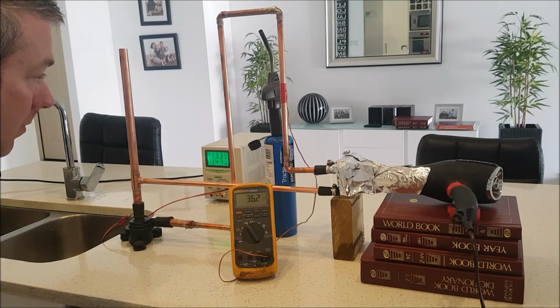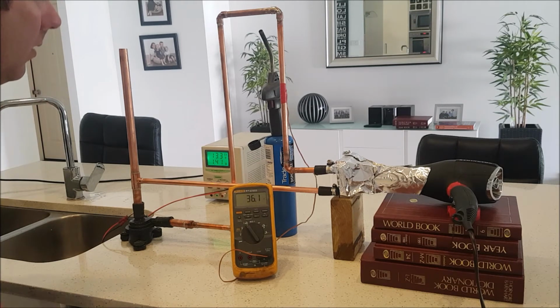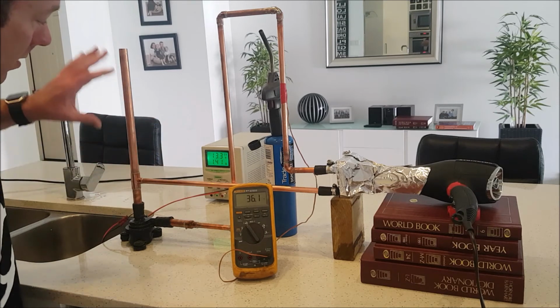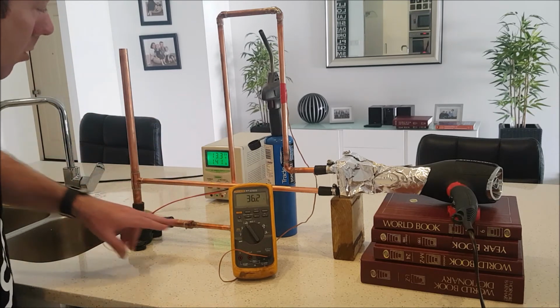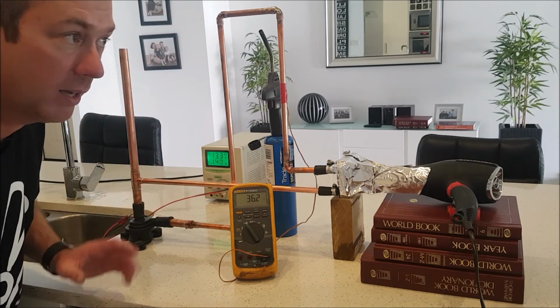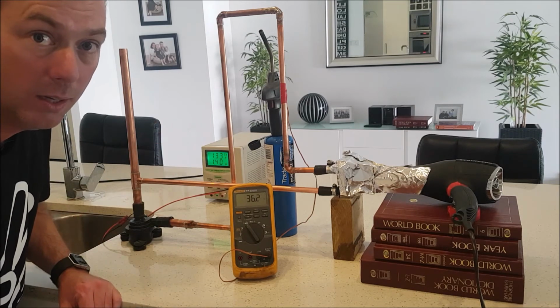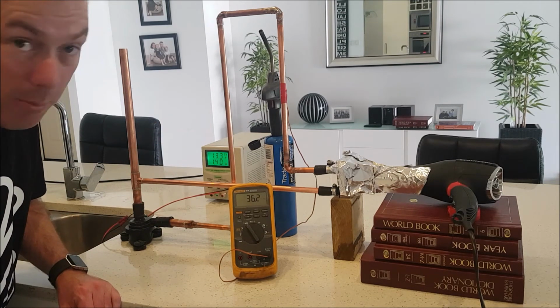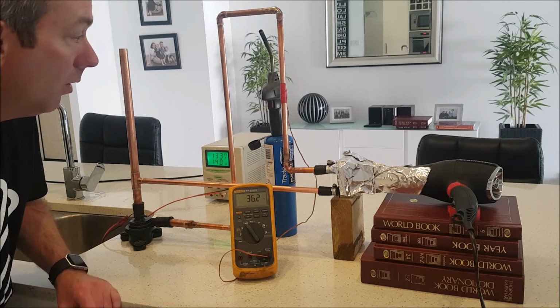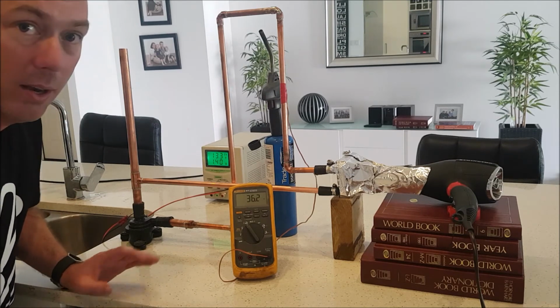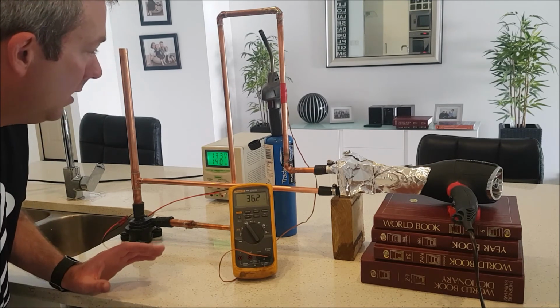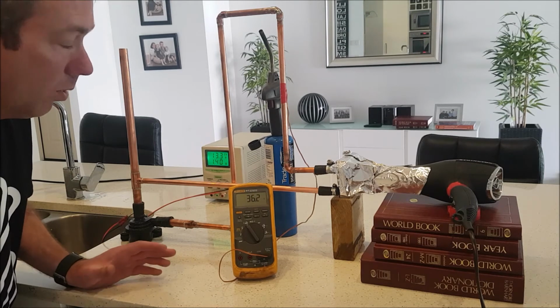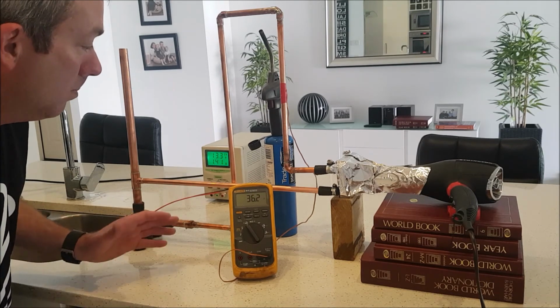So next, while this is running, it's moving the water around at 3 litres per minute. I calculated that earlier during the time lapse and made a mess everywhere, so I only took one measurement—it's crude, but that'll do. 3 litres per minute with water is 3 kilos per minute as mass flow.